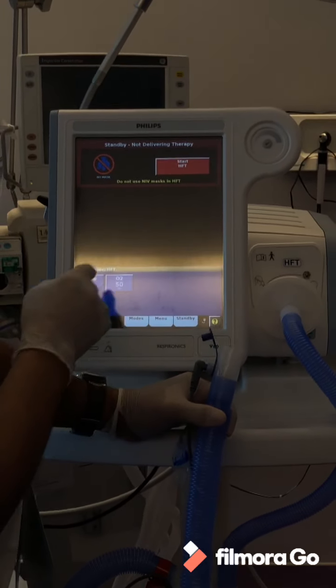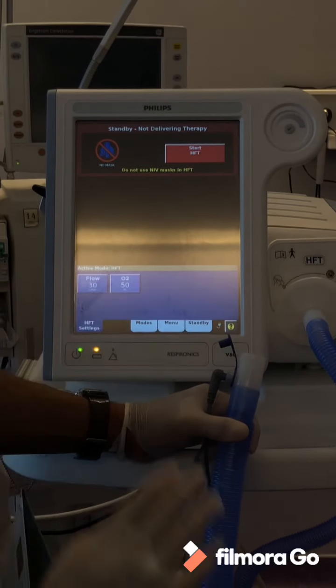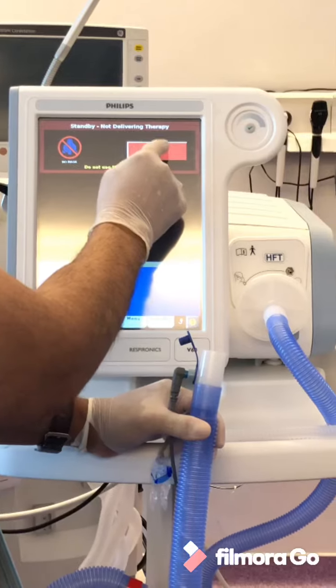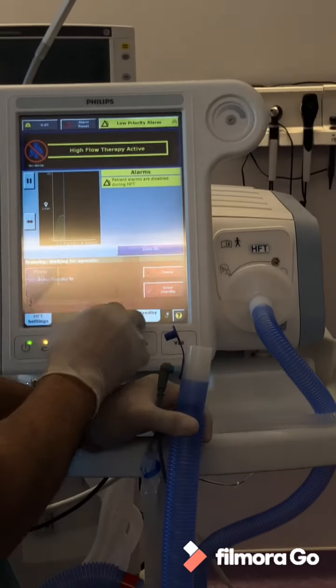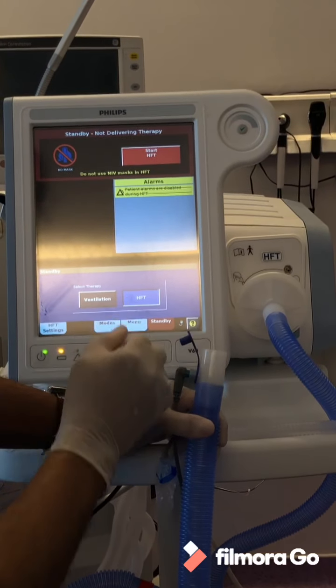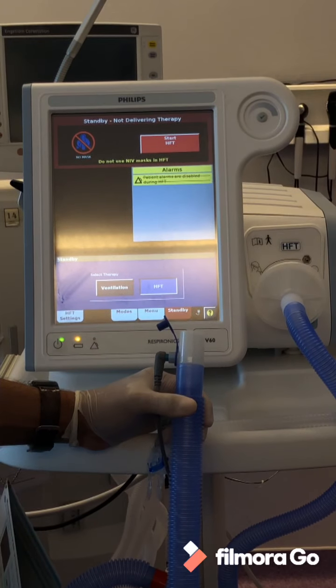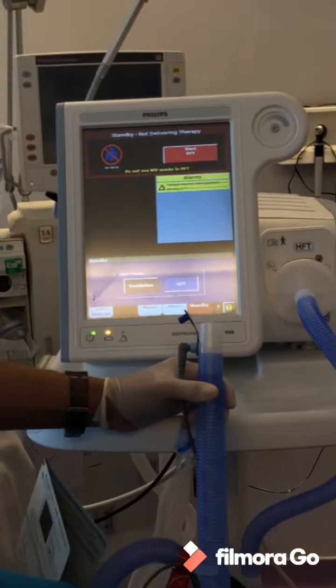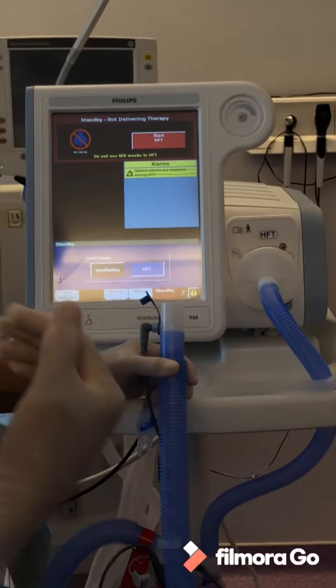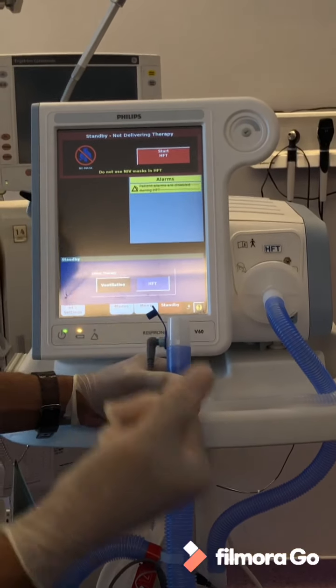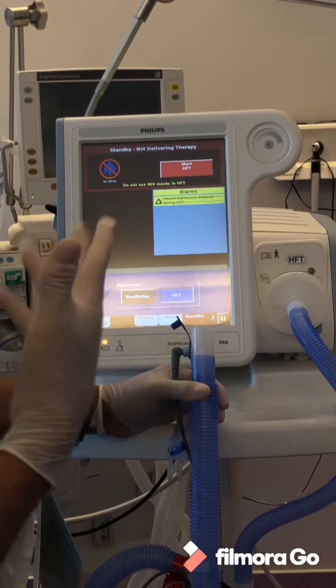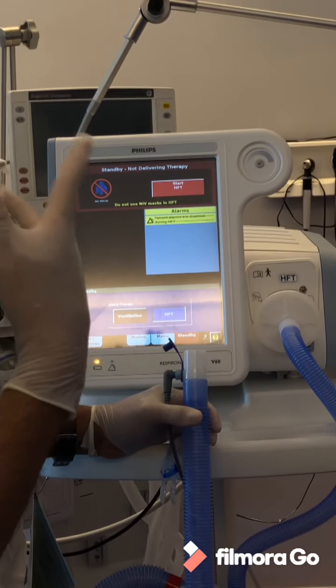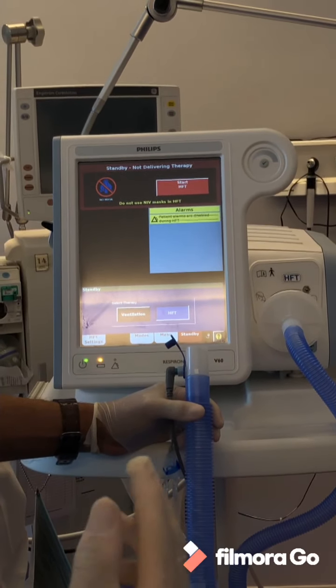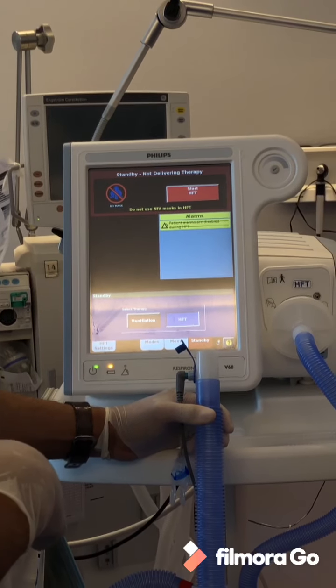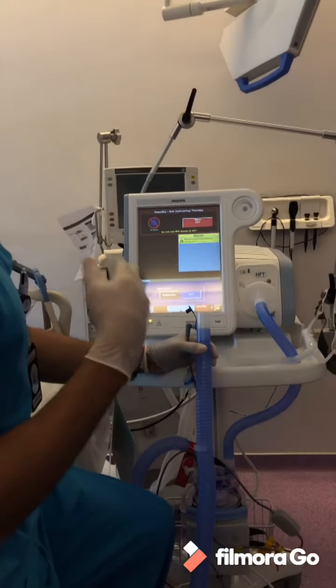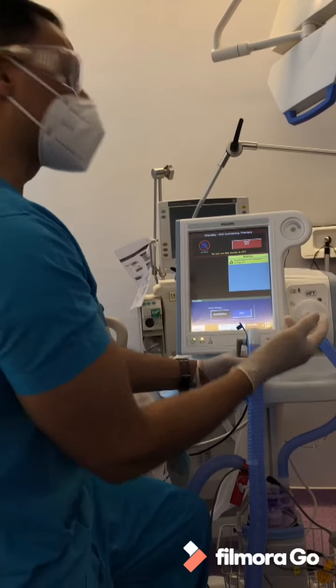You have only two options: to adjust the flow, and the FiO2. All right. If you want to start, you start the machine. But first of all, you have to make sure how to adjust your settings, the flow and the oxygenation. All of us at rest require 20 to 30 liters per minute flow. Okay, generate flow so they can carry the oxygen and it goes to the gas exchange. So if the patient is in distress and hypoxic, maybe a little bit tachypneic because of the hypoxemia, you want to start them at 60. So you want to start at high flow, and oxygen you can keep at 100 also.